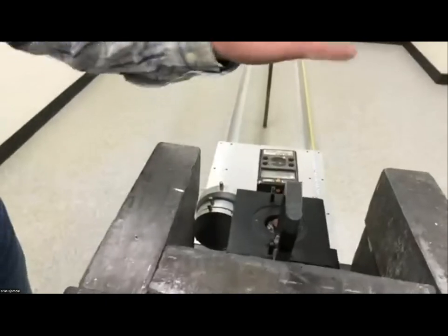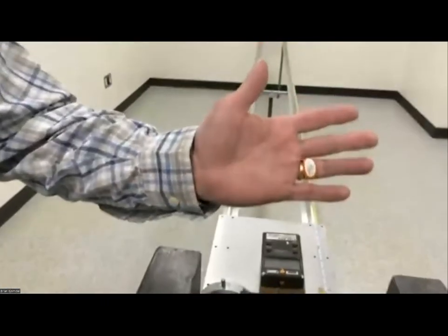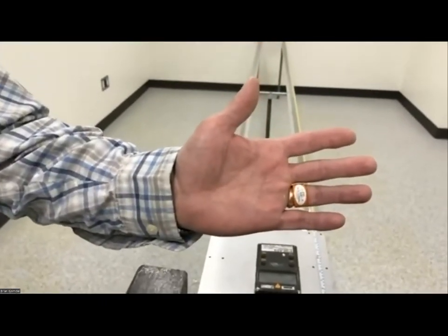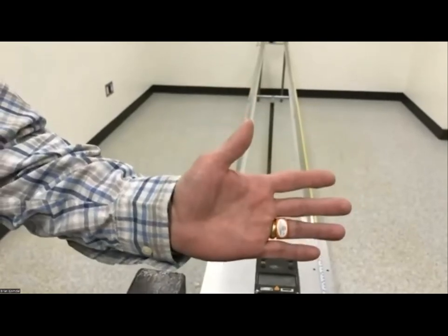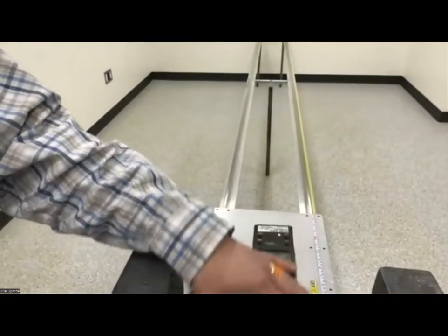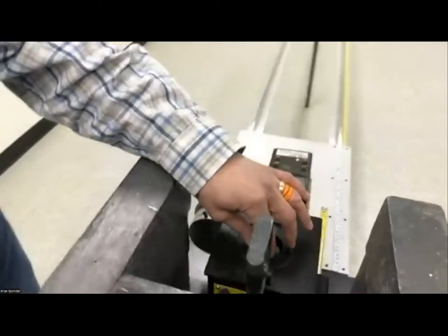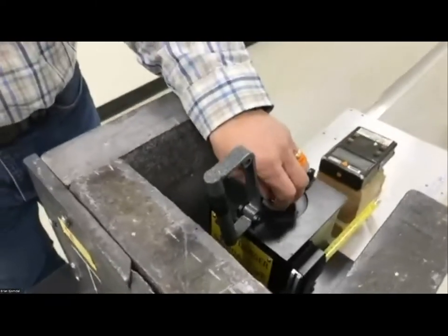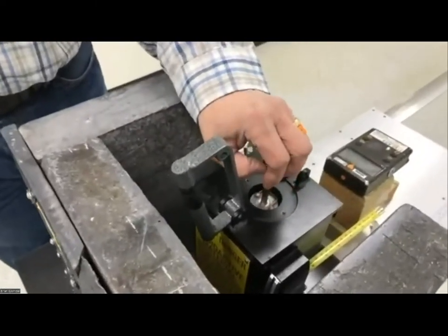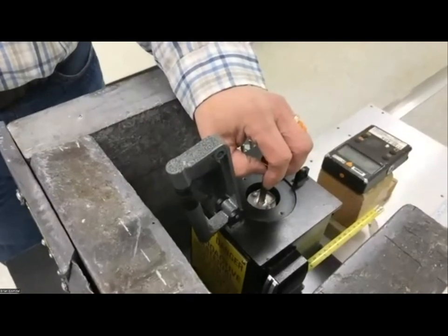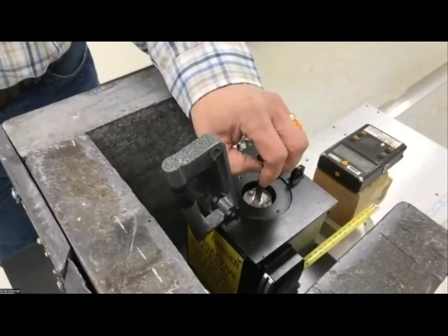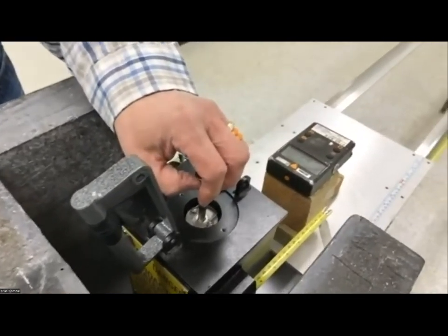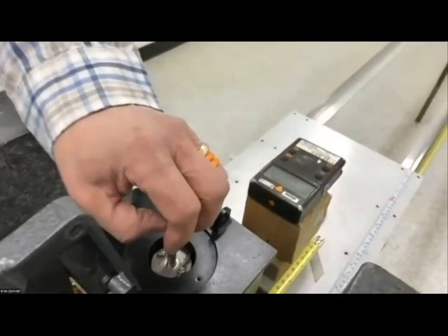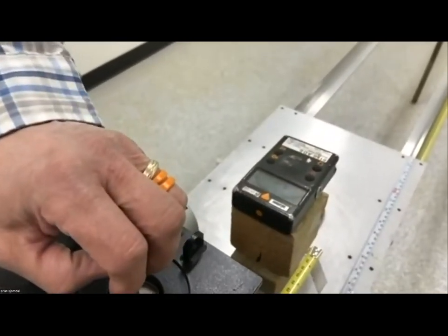So he's going to go behind the lead shielding here. To operate this device, you'll notice that I have a ring badge that I wear when we do this stuff, and that actually measures my extremity dose because my hand is going to be down here. To activate this source, there's a plunger on top. We pull the plunger, and that exposes the source. I don't know if you can see it on the display, we're looking at about 10 millisieverts per hour.